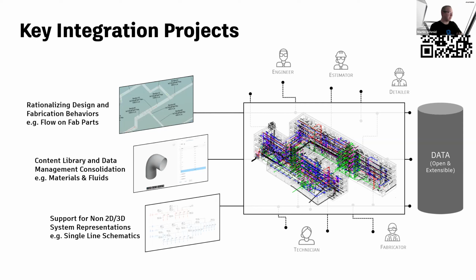Yeah, this is again steeped in capturing more analytical information and engineering data to automate these things and help facilitate change. One related aspect of the analytical representation is that at very early design stages, when you just have a switchboard with a feeder to a chiller or another panel, you already know you have a feeder. You likely already know the size—is that chiller or sub panel 400 amps, or a chiller with a 200 amp feed? At that stage you already know the conduit size and wire size. The only thing not yet accounted for at that conceptual stage is whether there's a voltage drop consideration that could upsize it.